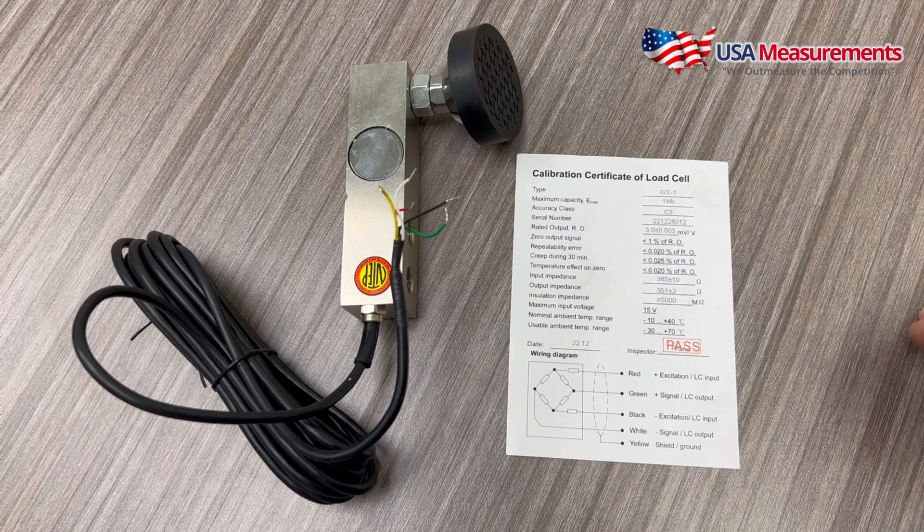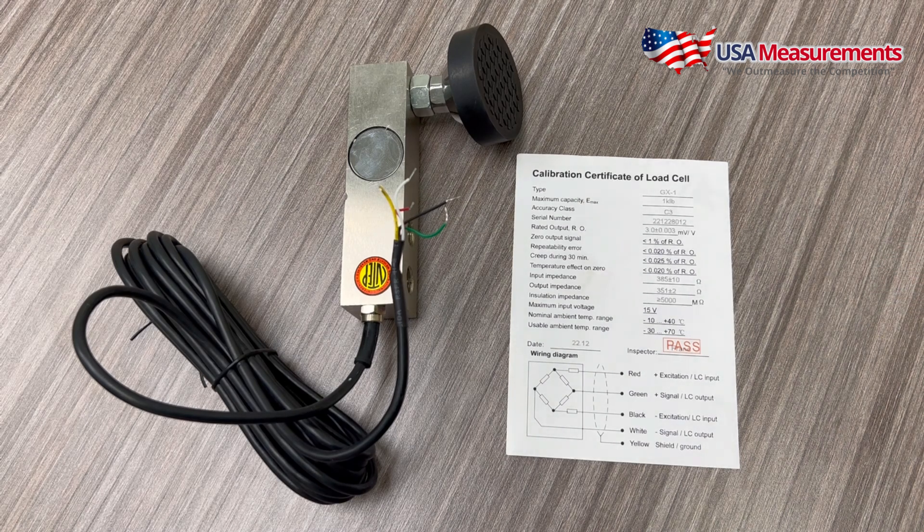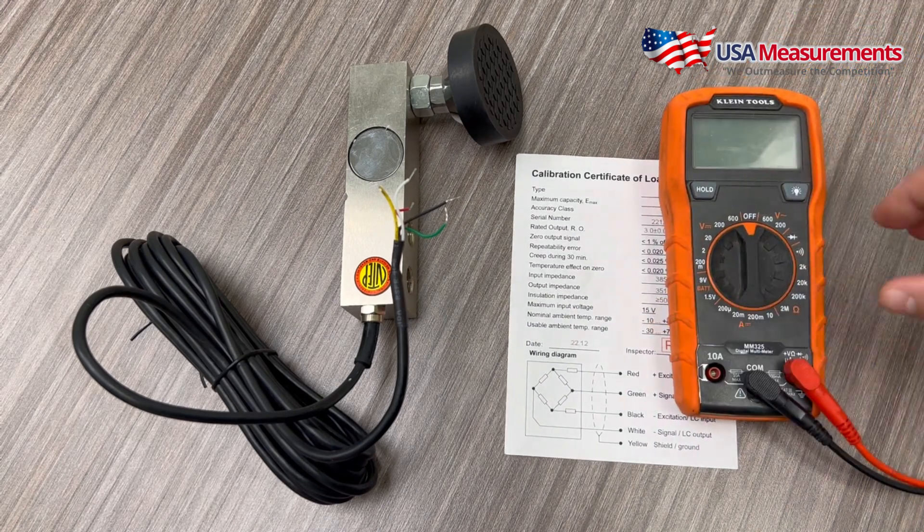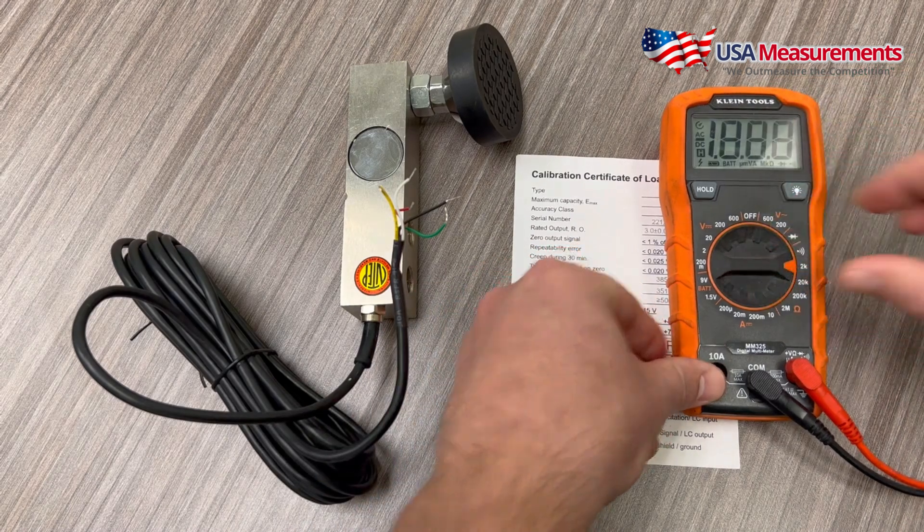are typically 350 ohms. That's what we're testing today. So what we'll need to do that is a voltage meter, and we want to go ahead and turn this on.